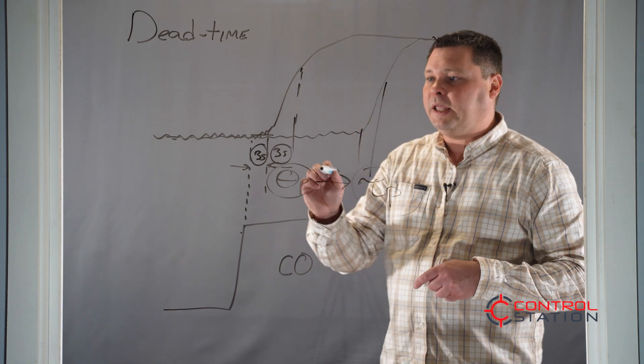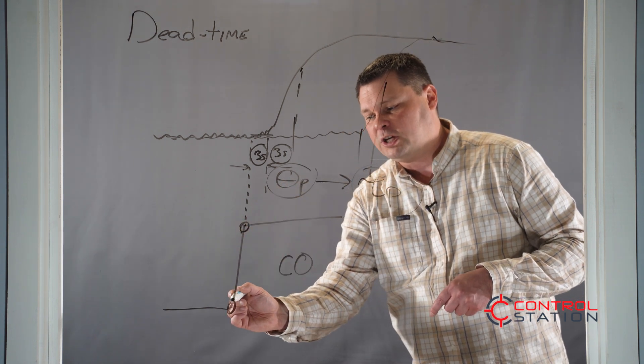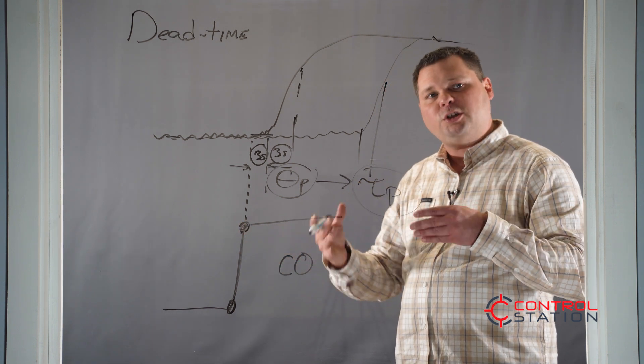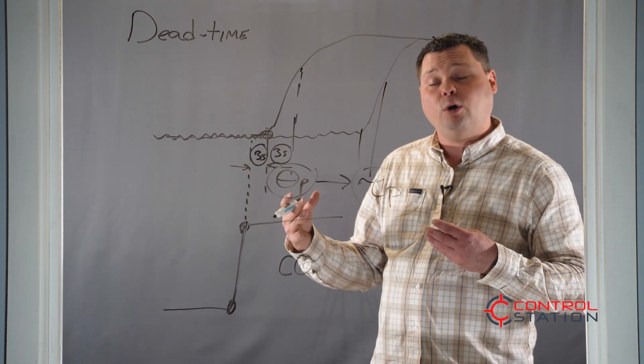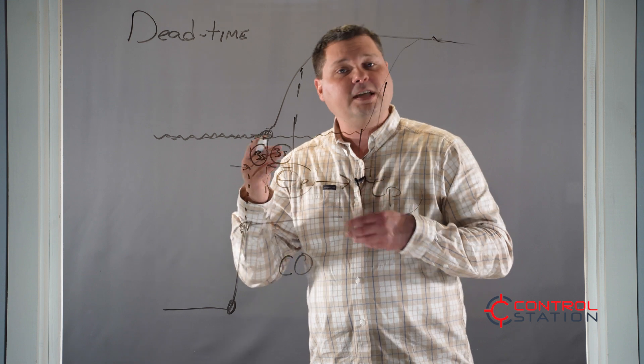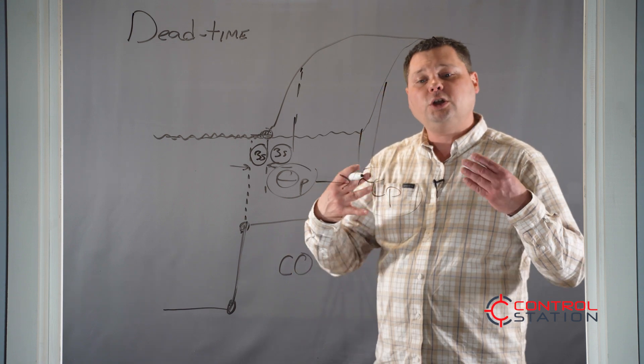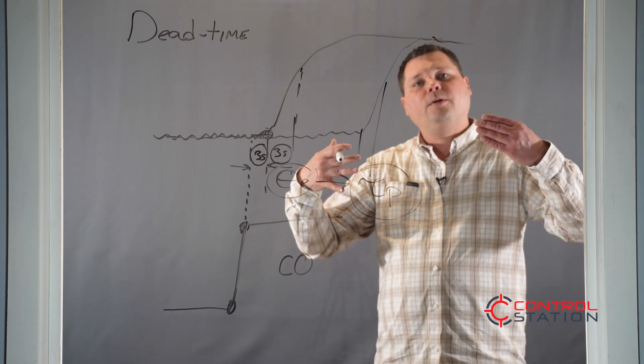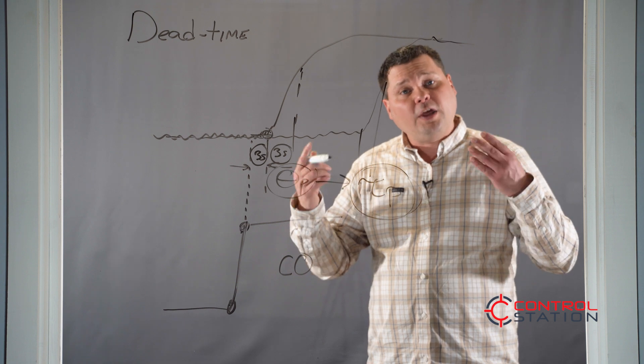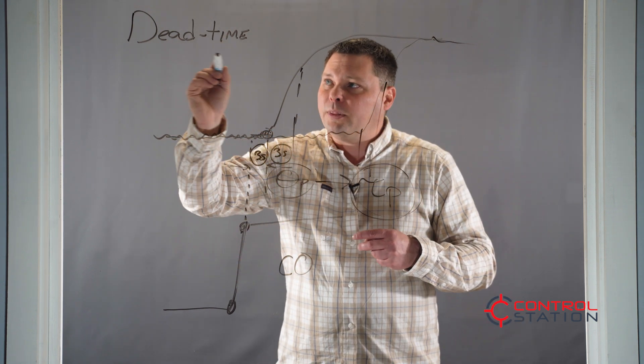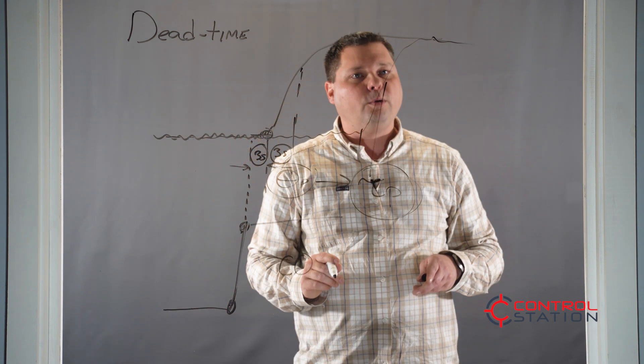So the dead time is related to the delay of the system. You measure from the time the controller output is changed — either the time you start the change or when it completes, just be consistent. You read the time off your process where it actually started to show a response, and you look at the difference. If it takes three seconds or five seconds, that's your dead time — it is the delay of the loop. The larger your dead time is relative to your process time constant, the more difficult tight, fast control becomes. Thank you for joining me in today's episode. We talked about the process dead time and how it's the time it takes from when you move the output to the process variable response.